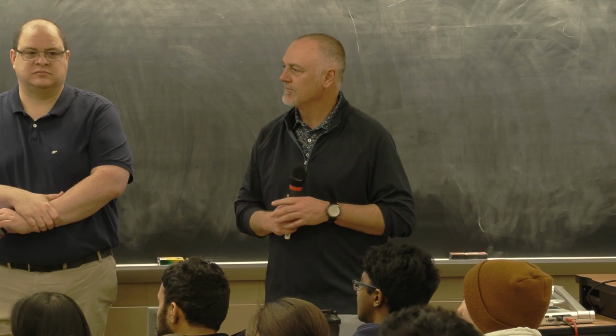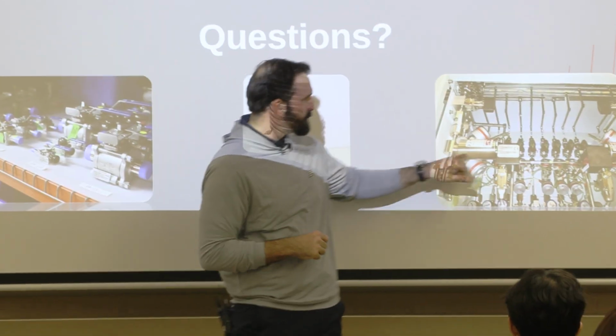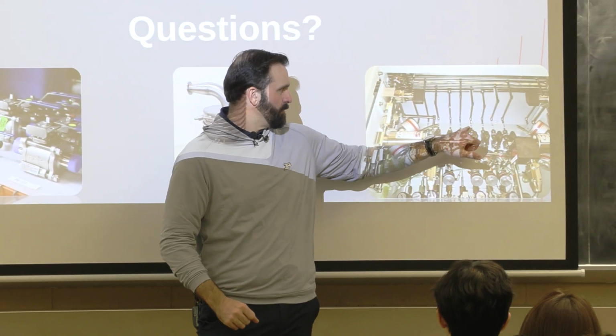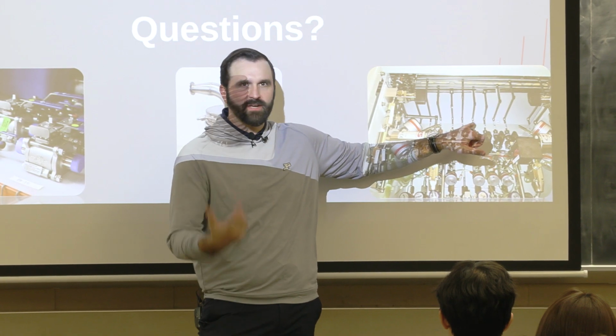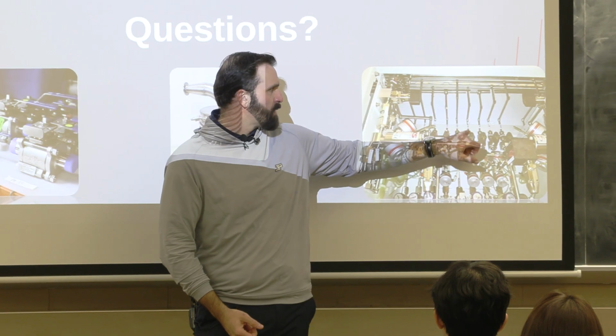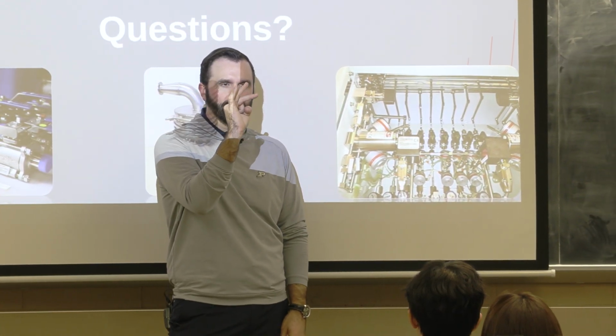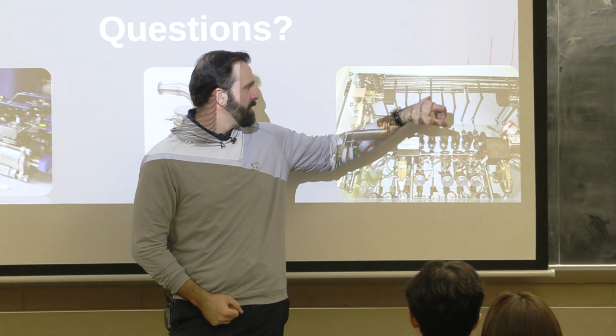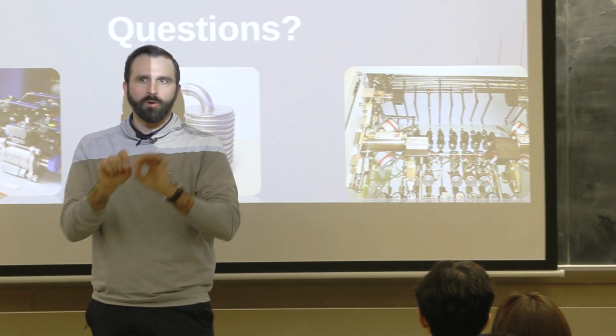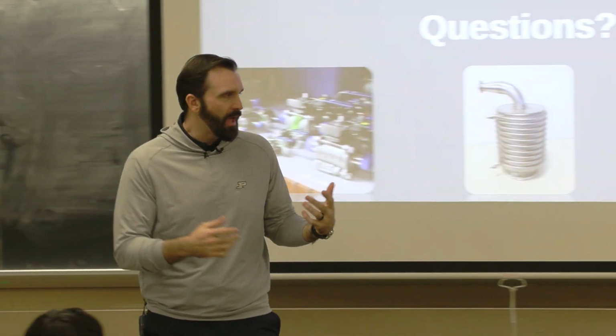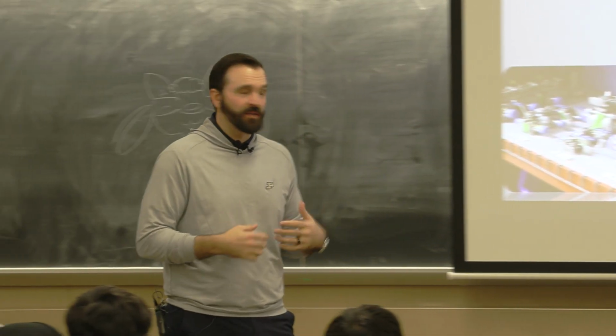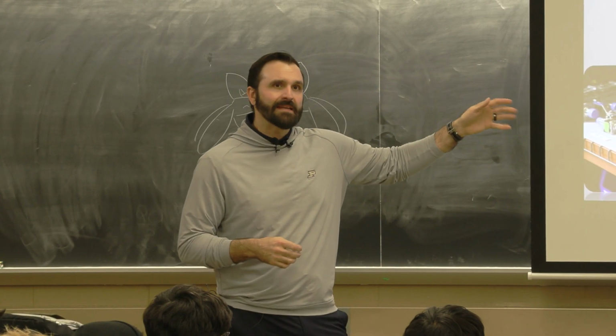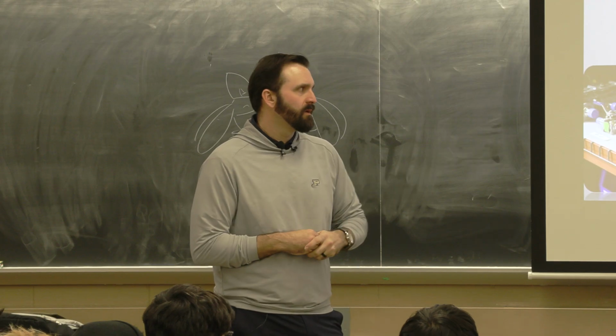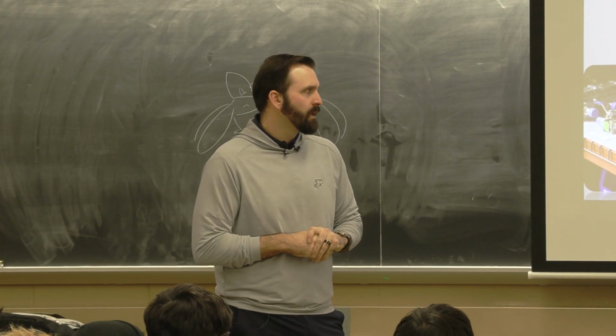When you look at something like this gas distribution box, these are all valves, but this tubing coming off of it is carrying some sort of gas - probably an eighth-inch piece of stainless tube that we have to weld together. Every turn is a fitting with 2 or 3 welds on it. Finding people who know how to do that to the level of cleanliness and quality required is few and far between.